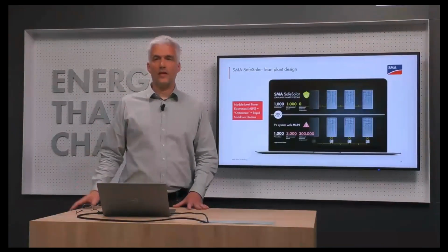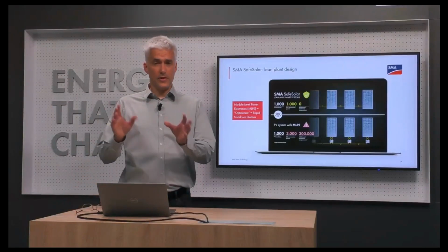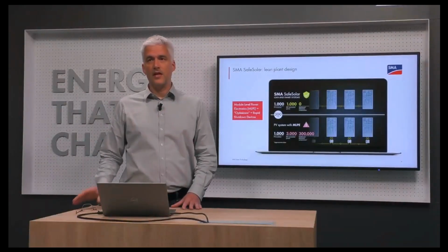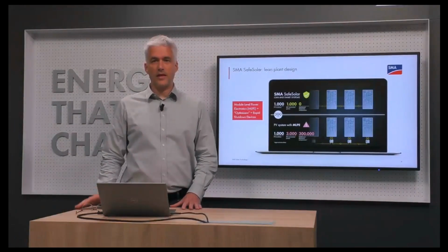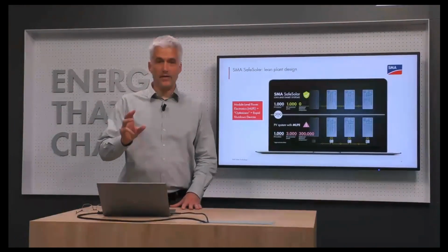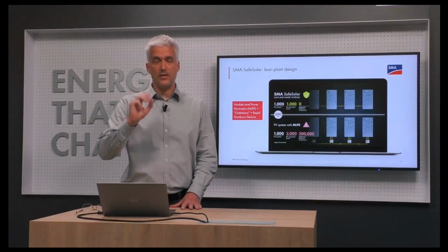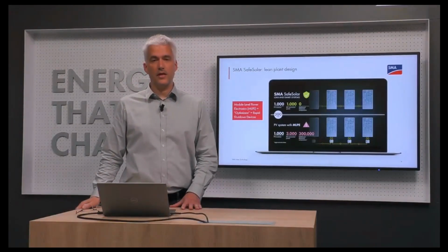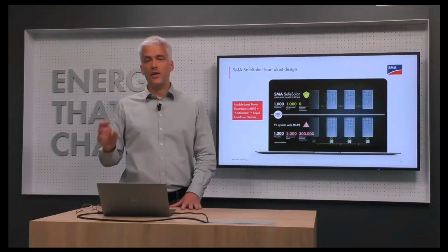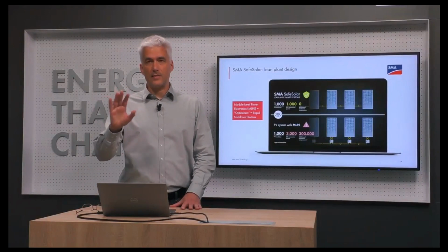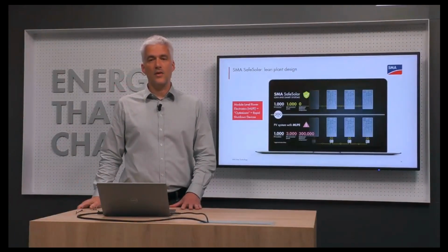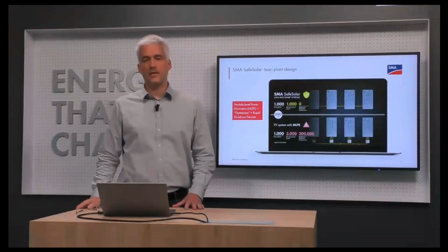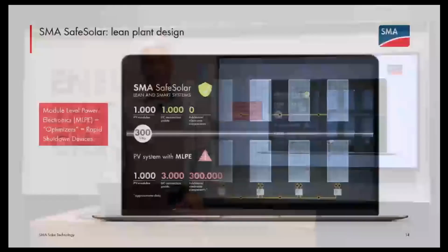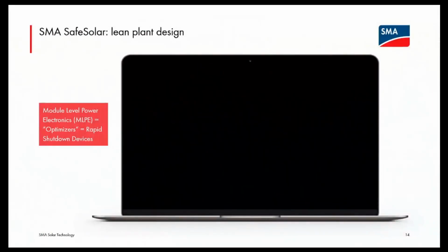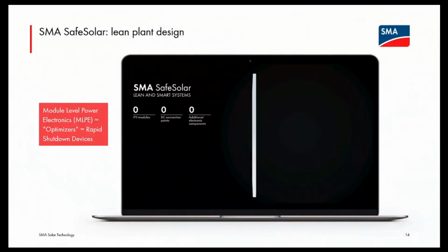For the module-level electronic system, of course, you've got PV modules with their connectors. You add all the module-level electronics. That means you're adding extra connectors, 3 times as many. Instead of 1,000, you've got 3,000 points of interconnection. And you're adding all the electronics. In total, a rough estimate for the 300 kilowatt system, you're adding 300,000 little electronic devices on your roof. On the roof, in an environment where, starting again for some reason.